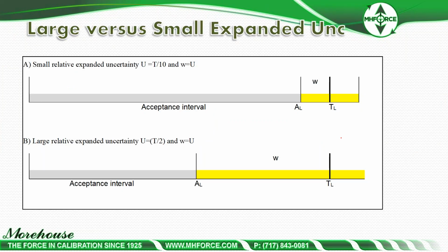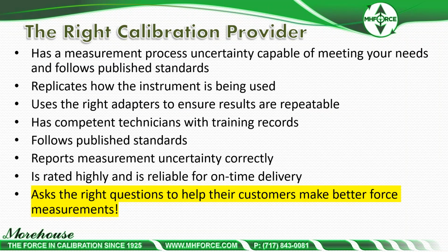Here's what we're saying. A small relative expanded uncertainty is going to give you a larger acceptance window. So look at labs with low CMC uncertainty parameters. If they're low, you're going to have more chance at an acceptance interval being larger. And if the CMC calibration measurement capability uncertainty parameter is high, the acceptance interval is going to be less. So they're going to call more things bad, and there's going to be more to deal with as far as recalling equipment, all the fun stuff that no one wants to deal with.